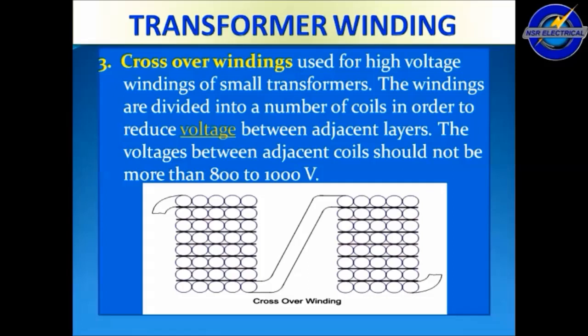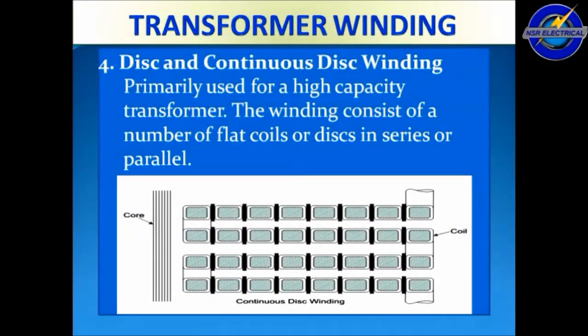The third one is crossover windings. Crossover windings are used for high voltage windings in small transformers. The windings are divided into a number of coils in order to reduce the voltage between adjacent layers. The voltage between adjacent coils should not be more than 800 to 1000 volts.